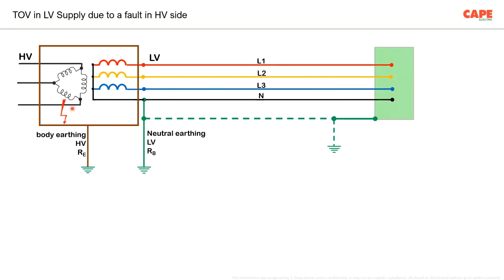Whenever there is a fault on the HT side of the transformer, one of the classic examples is a surge arrestor failure on the distribution or in an industrial premise. Whenever there is a surge arrestor failure on the high voltage side of the transformer, a lot of equipment at the low voltage side starts burning. The reason is, when there is a fault current through the earth electrode, it creates a high voltage, or a voltage gradient, at this particular location. This voltage gradient can be transferred to an equipment and your equipment may fail.